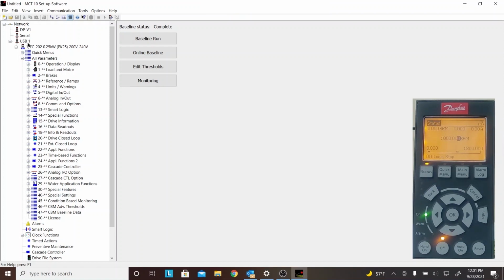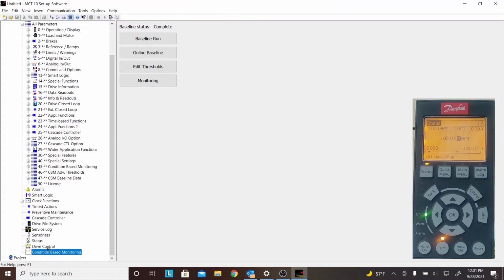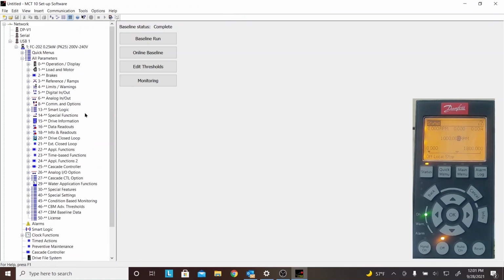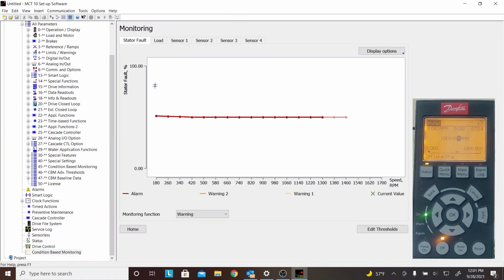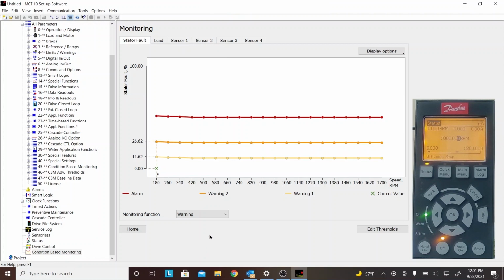You'll automatically bring it up under the USB. This is live, so you're always running live. We're not in a project. This is actually running live, and we can just click on the monitoring. Now, the software here gives you a lot of data on the drive and what's going on with the motor, etc. But the condition-based monitor is much further advanced.